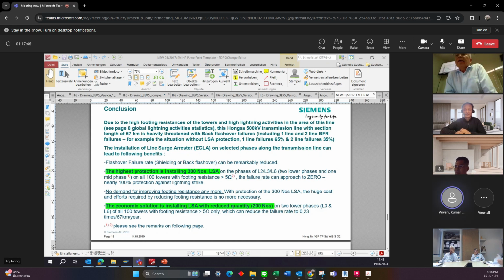Actually, in the lightning study there is a formula from the CIGRE paper that uses statistical analysis, which divides the lightning current throughout the different spectrum, so different values will be applied on the towers. Based on the geometry and the insulator behavior on that tower, it will show how many back flashovers occur, at what level of lightning current it gets flashover, and what the back flashover rate is if we don't install any surge arrestor. And if I add the arrestor installation, how much improvement we can get through that statistical study will also be showcased by the line study.